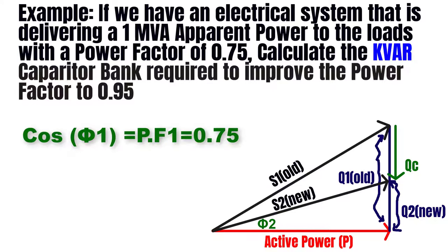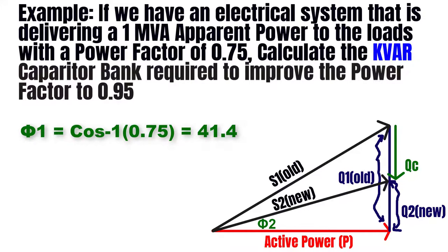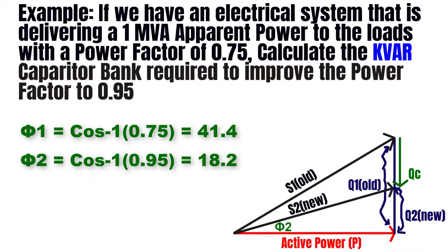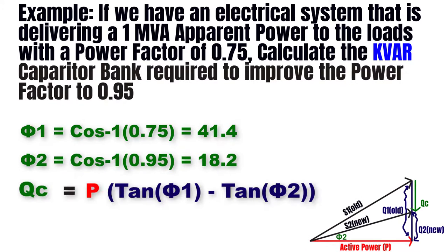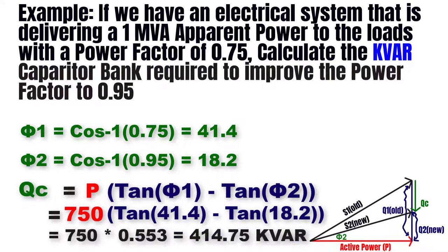We have the old power factor of 0.75 and the new one of 0.95. Phi 1 equals cosine inverse of 0.75, which equals 41.4 degrees. Phi 2 equals cosine inverse of 0.95, which equals 18.2 degrees. Back to our equation: Qc equals P times (tan phi1 minus tan phi2) equals 750 kW times (tan 41.4° minus tan 18.2°) equals 750 times 0.553, which equals 414.75 kVAR.